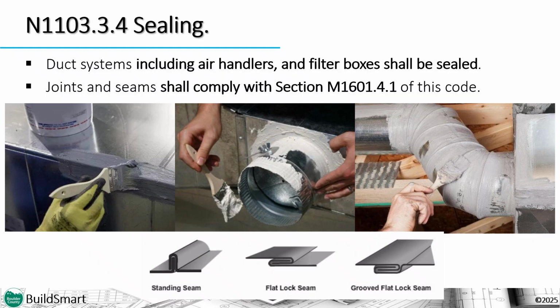At the levels of tightness required by the code, the manufactured joints will leak as well, so make sure that they are sealed and sealed well. This includes boots or elbows and seams at duct boots. In addition, the air handler is required to be tested by the manufacturer not to leak more than 2% of the designed flow. That could be enough leakage to fail a duct test, so don't be afraid to air seal the cabinet itself. Filter slots are required to be airtight and cannot be taped off during a duct test.